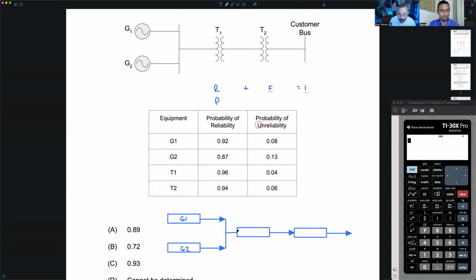They're in parallel, meaning generator number one is big enough by itself, and generator number two is big enough by itself to provide power to the customer, so the path can take either direction in this block diagram. Transformer T1 and transformer T2, we've modeled their probabilities in series, because if I lose T1, it doesn't matter what the generators are doing—customer's in the dark. Same thing if I lose T2. That's why we're modeling transformers one and two in series in our block diagram.